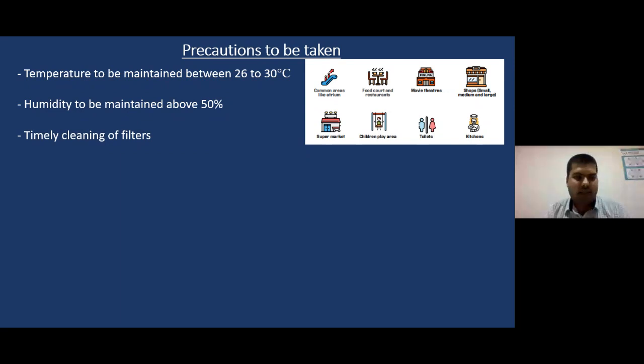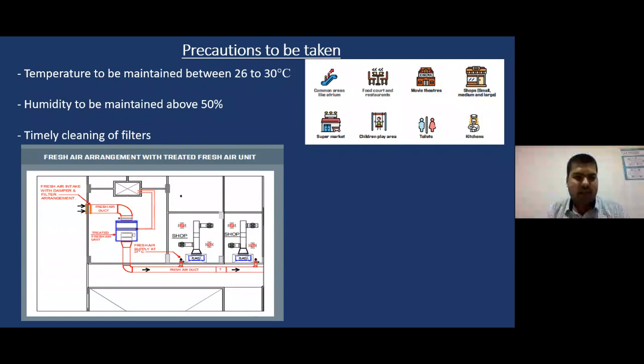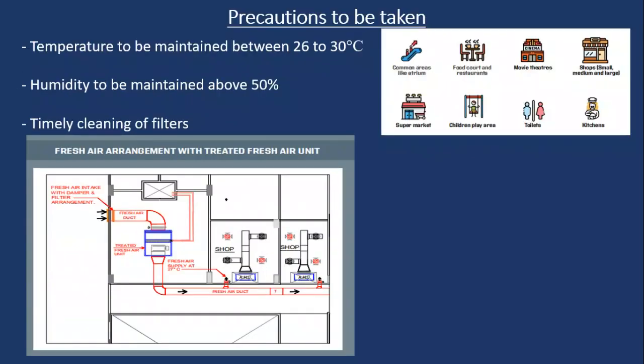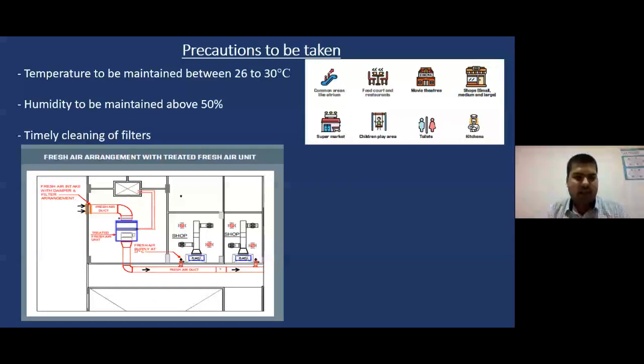Also, there's something called fresh air, which is the most talked about topic. In systems with AHUs or air conditioning units, where does the fresh air come from? Normally, a machine called a treated fresh air unit can be installed. It takes fresh air through a duct from the outside, reduces its temperature, and passes it through that particular shop or room. This fresh air duct can be incorporated in the current existing machines as well as new machines. The fresh air component, which was mostly neglected by the air conditioning people as well as customers, needs to be added. What fresh air does is increase the air changes in that room, so that fresh air is maintained and there is proper ventilation.